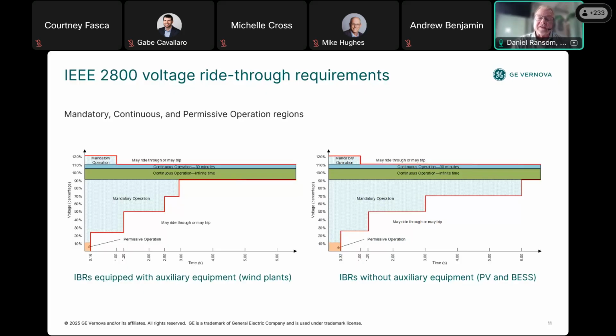The IBR must provide pre-disturbance active power or minimum available active power while adhering to the maximum current limit, Imax. After 1 second during the overvoltage period, or the overvoltage levels from 1.1 to 1.2 per unit, in that period the IBR may trip or continue to ride through. Tripping or current blocking prevents IBR damage. As we go lower in voltage into the mandatory operation region from 0.1 to 0.9 per unit, the low voltage ride-through region, the IBR must inject current to the maximum limit Imax to support grid stability. After the specified time at a voltage level, the IBR may trip or continue to operate. The standard requires automatic voltage control during ride-through while adjusting fault current fundamental frequency, and I'll show that in a moment, depending on the voltage deviation from normal.